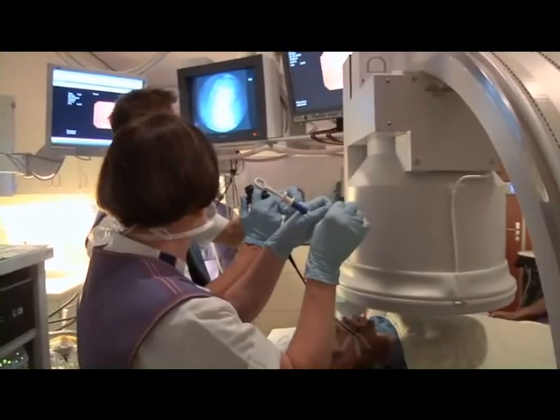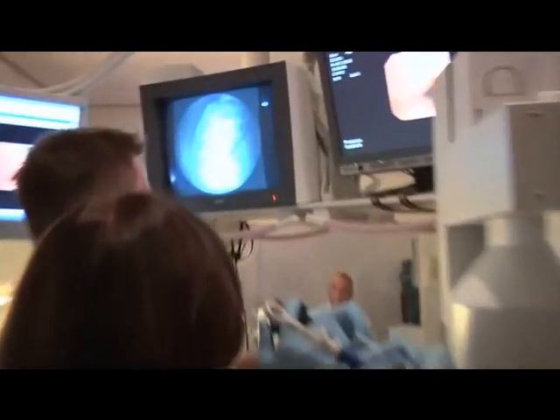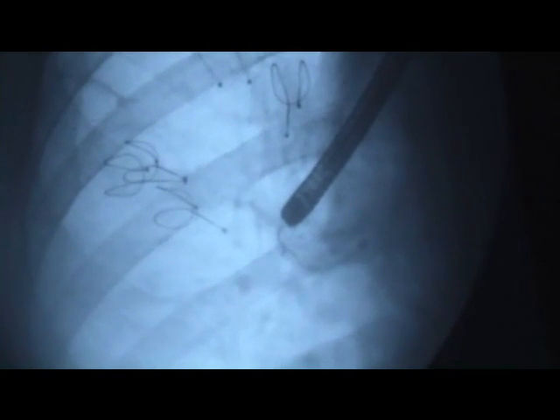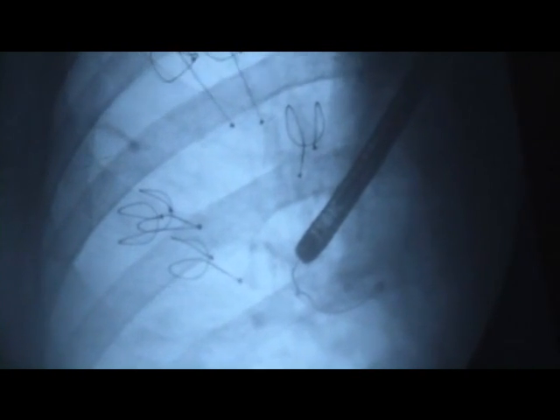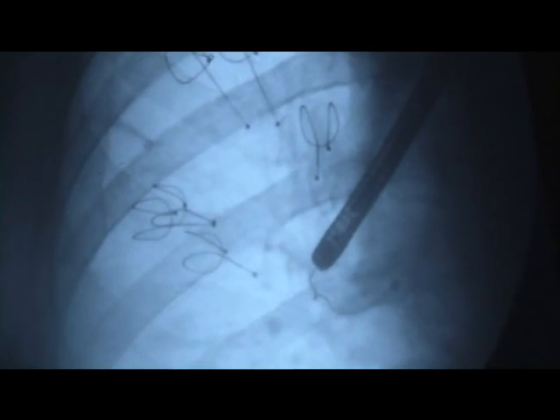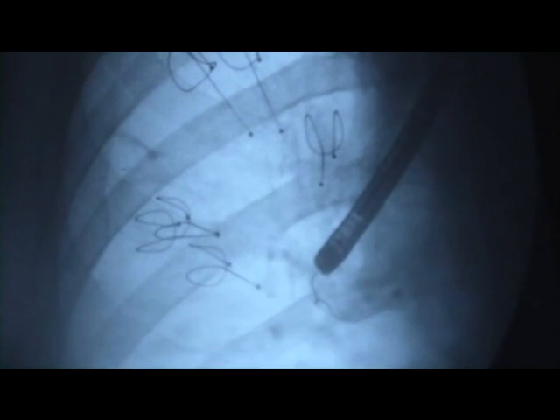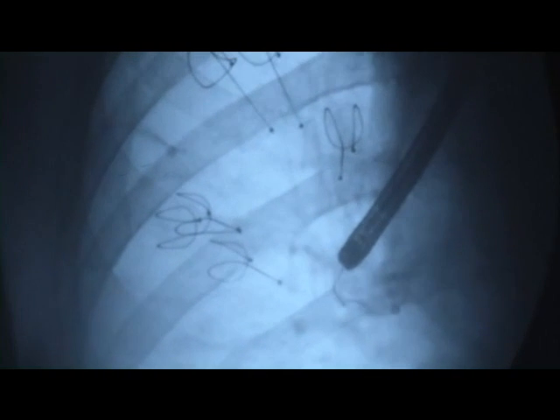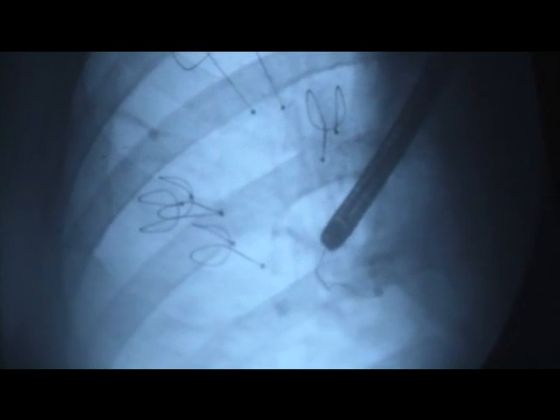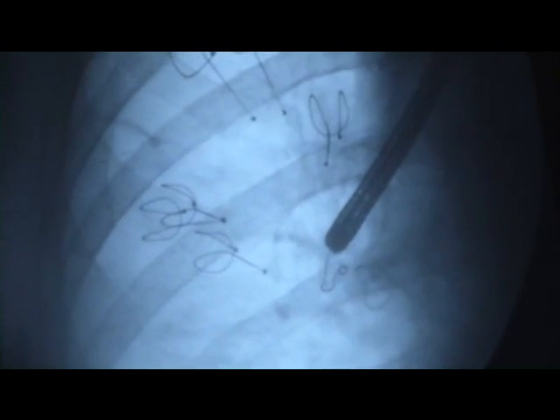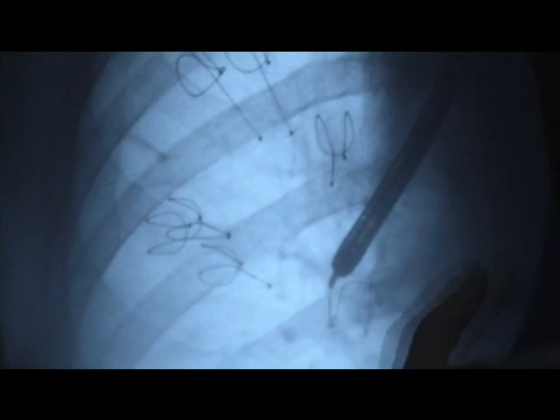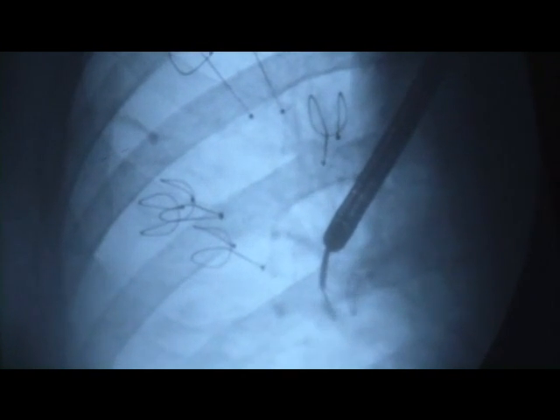So you can see the coil coming through the bronchoscope, and we align the coil with the distal end of the catheter. Okay, and through the bronchoscope you can see the biopsy forceps head. So now we first retract the catheter a little bit until the coil makes the first bend like this, and now we advance the coil and retract the catheter at the same time and make sure the biopsy forceps head stays out of the bronchoscope.